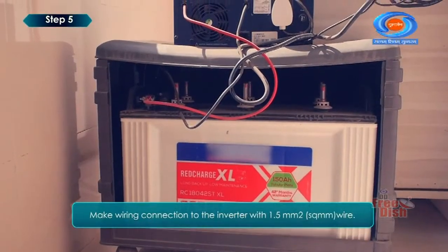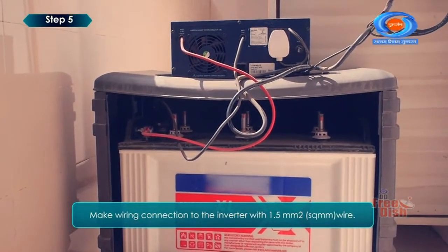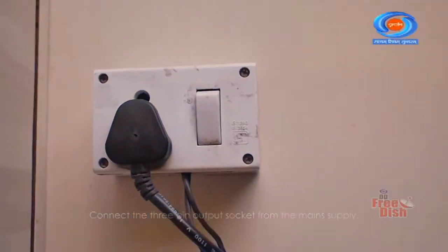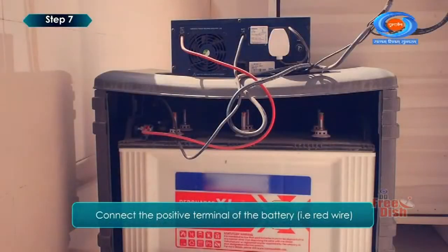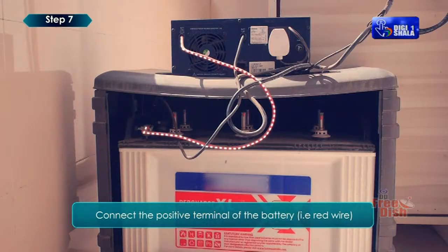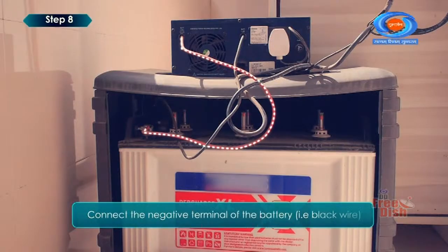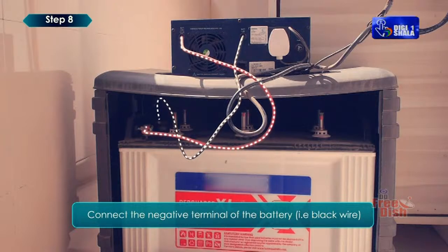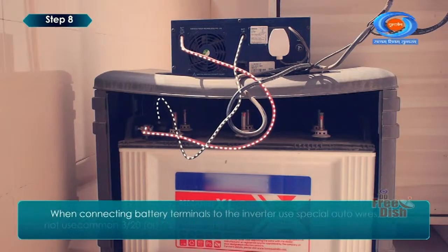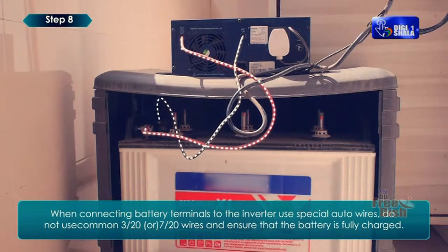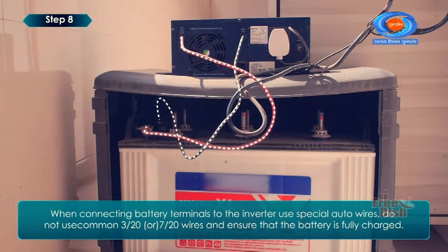Step 5. Make the wiring connection to the inverter with 1.5 square millimeter wire. Step 6. Connect the 3-pin output socket from the mains supply. Step 7. Connect the positive terminal of the battery, that is, the red wire, to the place provided for the positive terminal on the inverter. Step 8. Connect the negative terminal of the battery, that is, the black wire, to the place provided for the negative terminal of the inverter. When connecting battery terminals to the inverter, use special auto wires. Do not use common 3x20 or 7x20 wires, and ensure that the battery is fully charged.